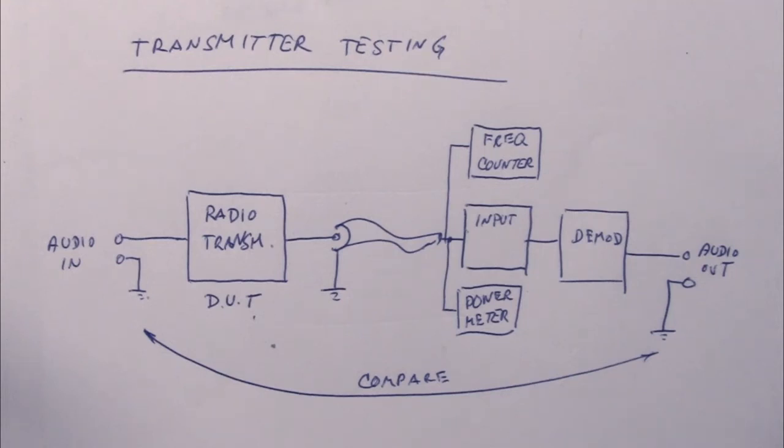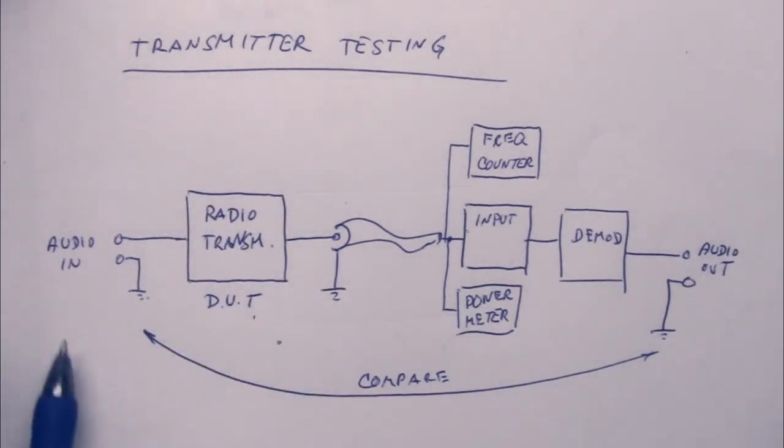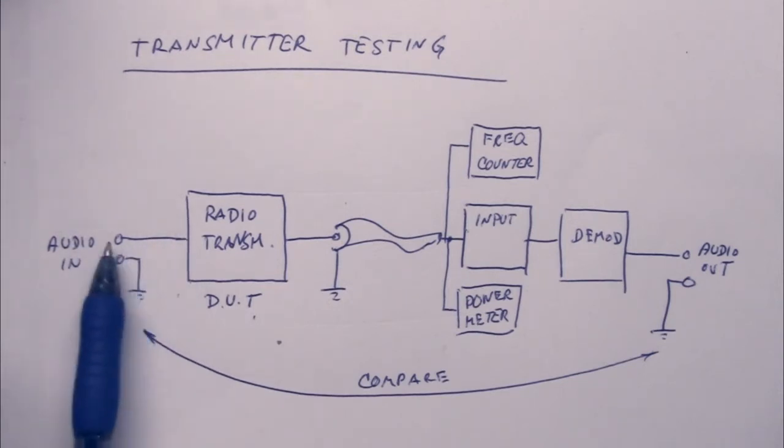Hello there and welcome. We're testing radio transmitters. Basically what you do is you have your radio here, your transmitter here, and you inject an audio signal. It's typically one kilohertz, but it could be other things as well.